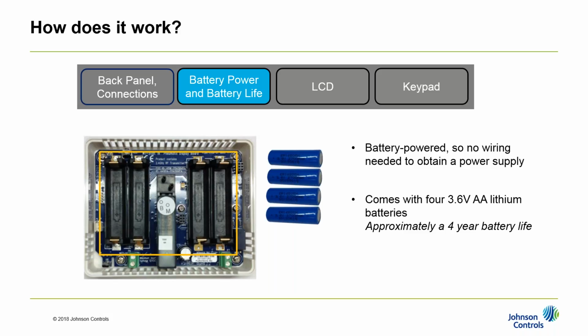Typical battery life is about 4 years, since it's a somewhat energy-hungry application due to running that piezo valve, but we get about 4 years battery life in a typical system. This will actually improve if your system is well maintained - the more times it has to actuate and change pressure in the line, the lower the battery life will be, so if well maintained you can see well upwards of that. The batteries themselves have a shelf life of 15 years, so you can get quite a bit above 4 years with a well installed system.